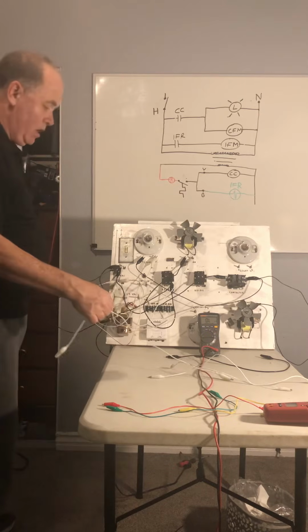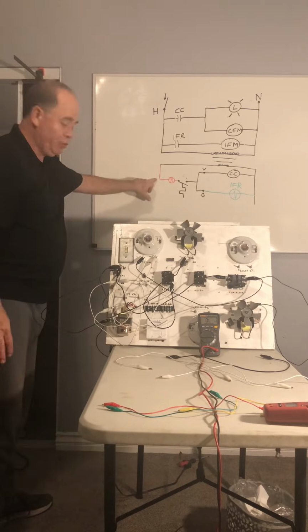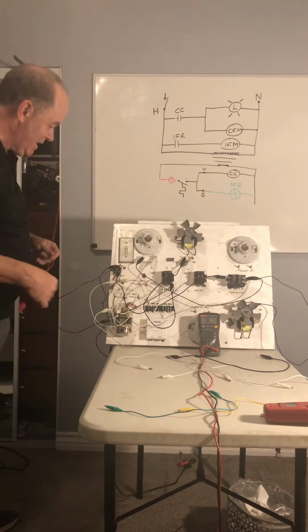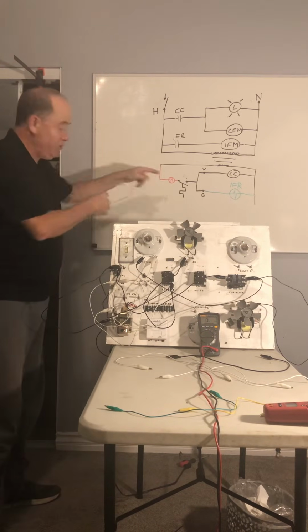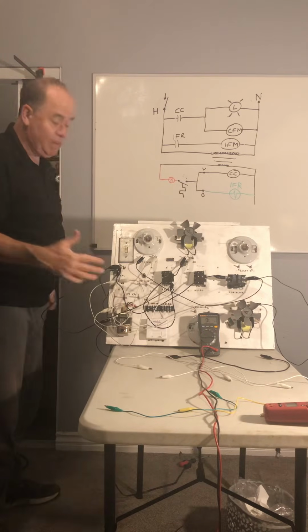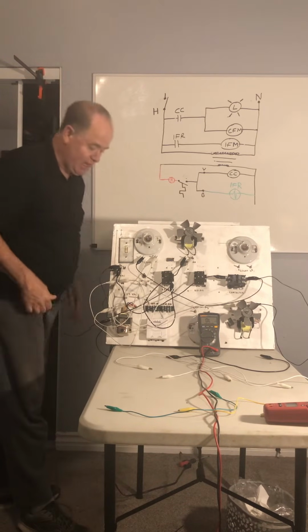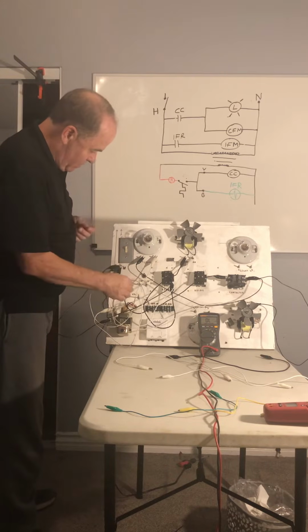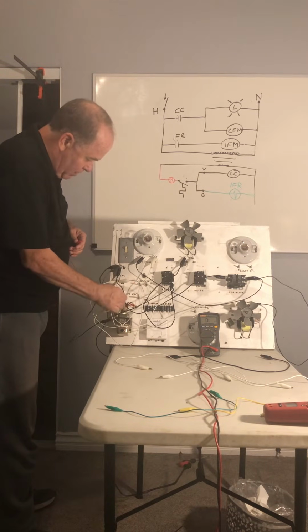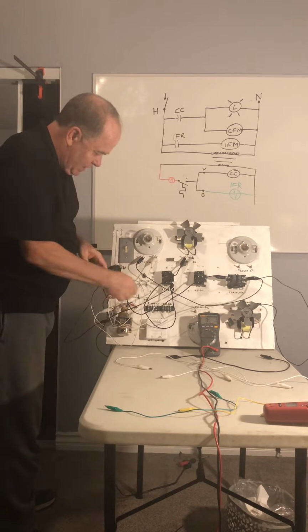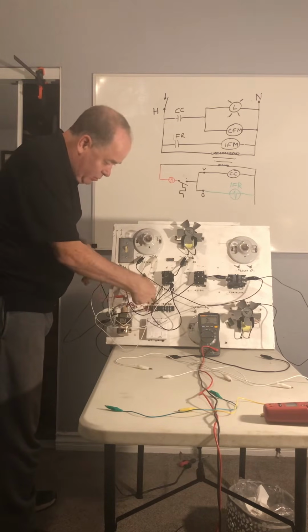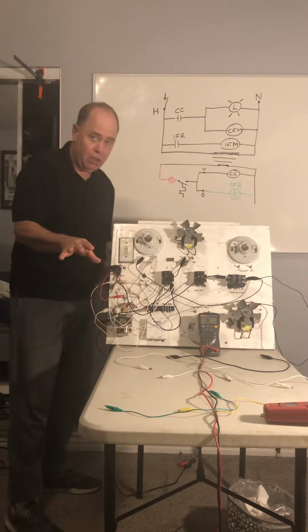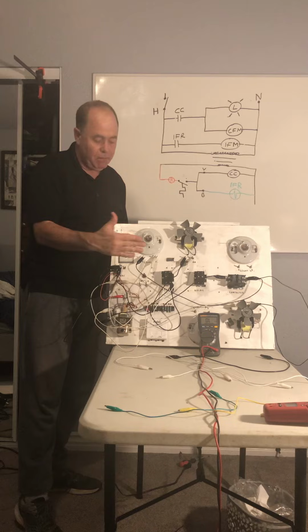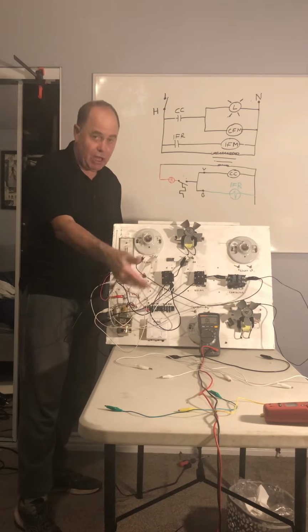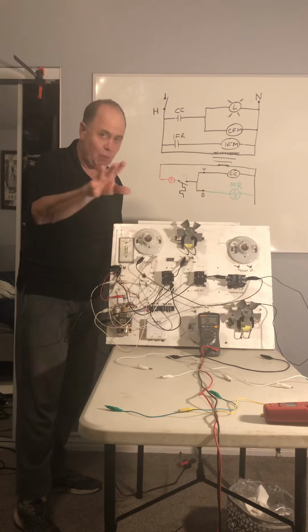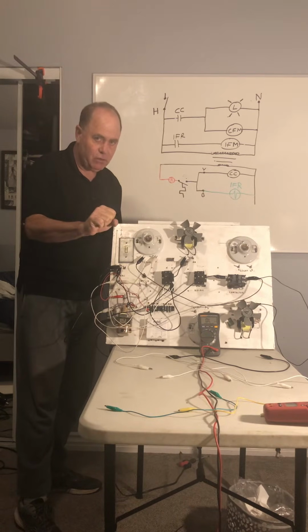And now we're working on the low voltage side. We come off of the secondary of the transformer, and we're using red because that's the color that is typical for power for the thermostats. Here we're coming off the secondary of the transformer, and you have terminals like this on the back of your thermostat, normally on the sub base, but here for convenience we have a terminal block, and it's pre-wired for us, but we're still doing the same wiring activity that you might have to do in the field.